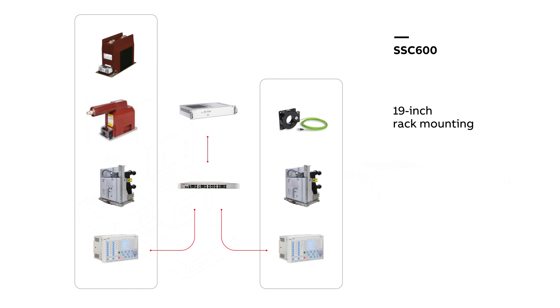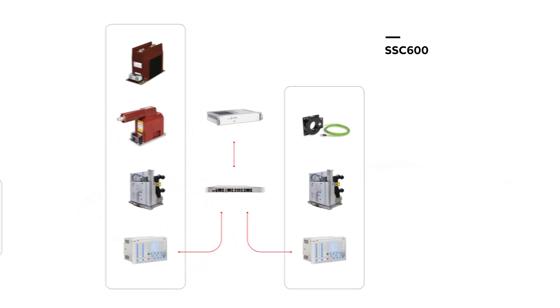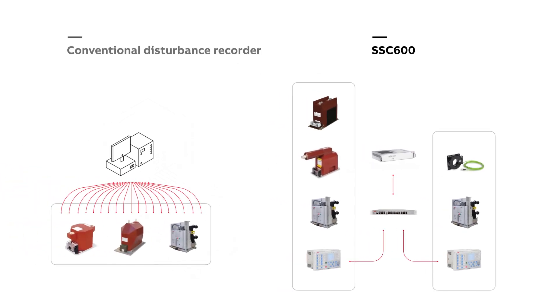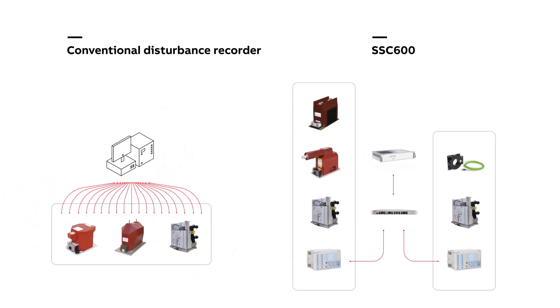To simplify and have a more efficient approach, we can change the conventional technology to sensors and process bus. This way, instead of having 400 wires, we can have a lot less wiring with fiber optic and galvanic cables. We can have 20 or fewer Ethernet cables connected to the switch.